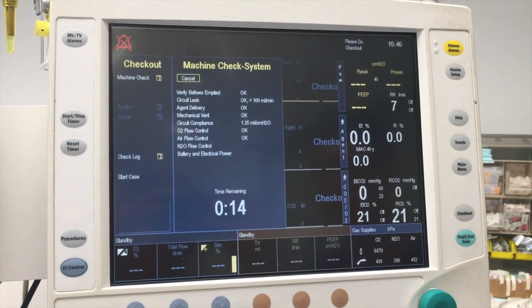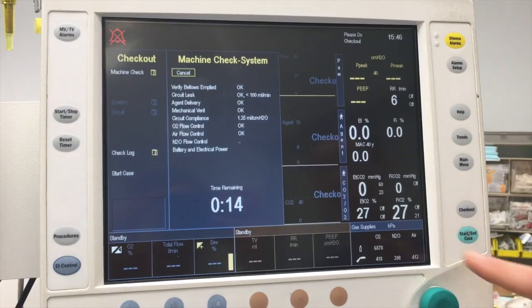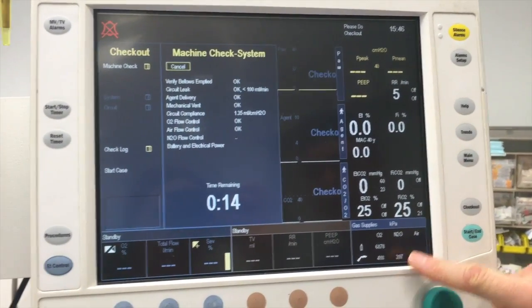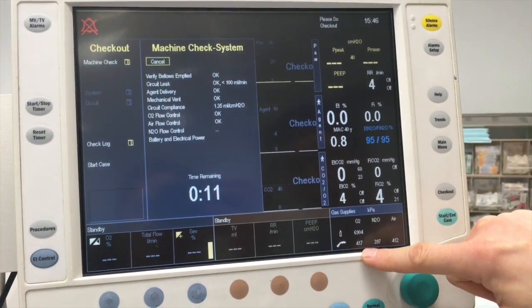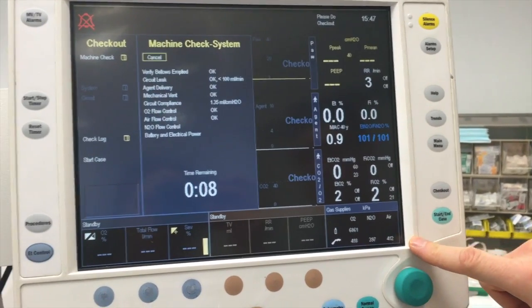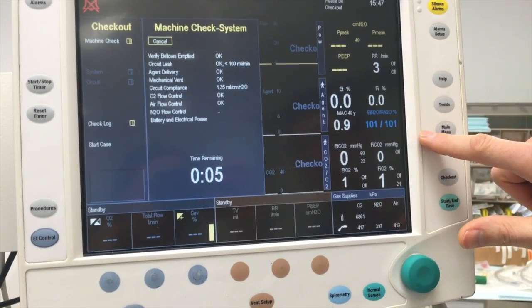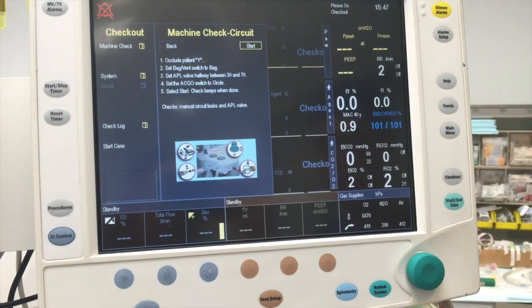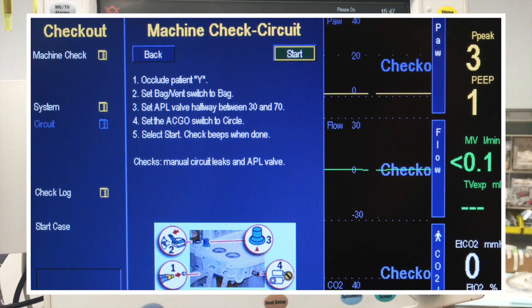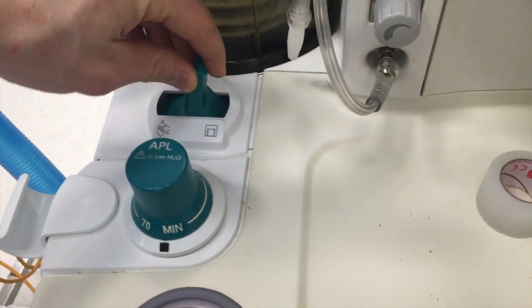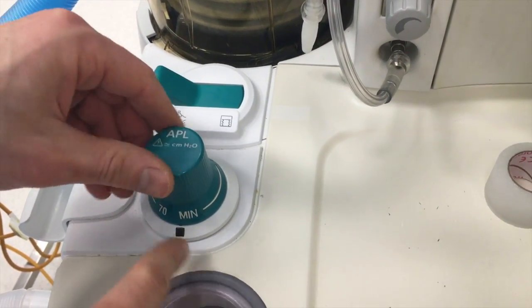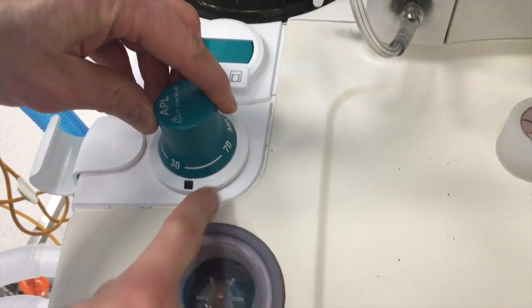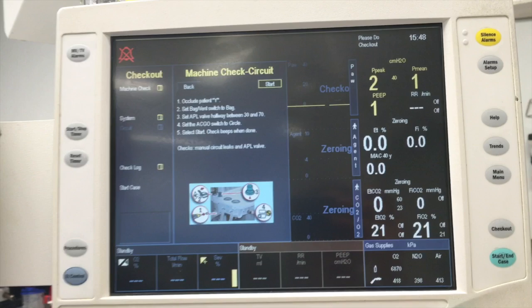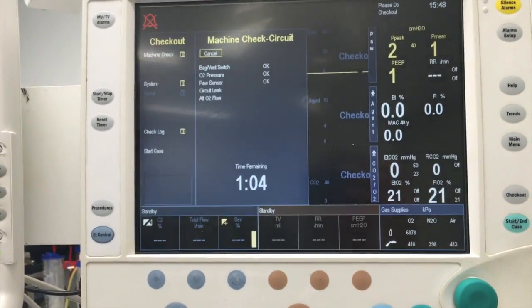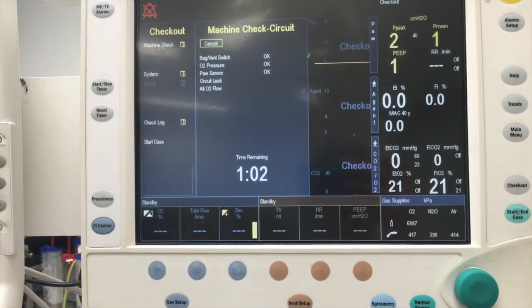As this part of the check almost comes to an end, you can see all the things the machine has checked. And if you watch closely, you can see it doing its final checks of oxygen levels and also nitrous levels. Once the automatic breathing system check is done, the machine prompts you to get ready for the automatic circuit check. Set the bag vent switch to the left and adjust the APL valve to between 30 and 70. Once you confirm Start with the green control knob, the machine begins its final automatic check.